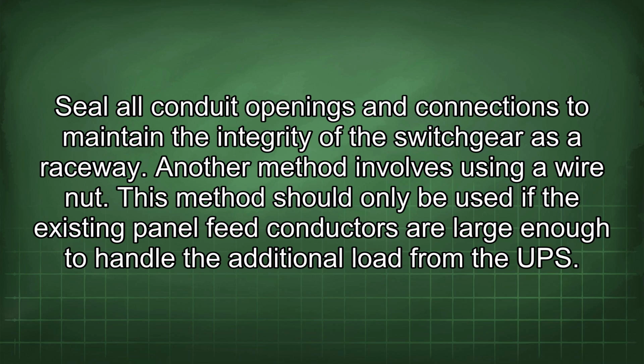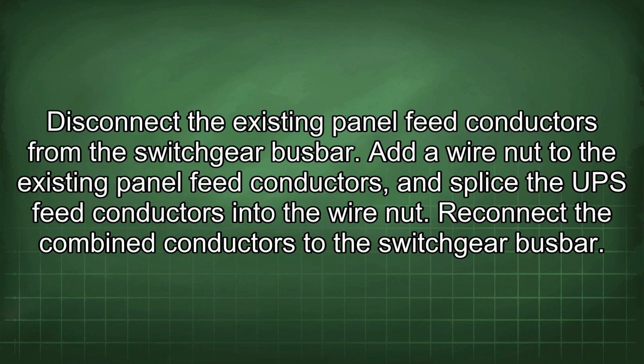Another method involves using a wire nut. This method should only be used if the existing panel feed conductors are large enough to handle the additional load from the UPS. Disconnect the existing panel feed conductors from the switchgear busbar. Add a wire nut to the existing panel feed conductors and splice the UPS feed conductors into the wire nut. Reconnect the combined conductors to the switchgear busbar.